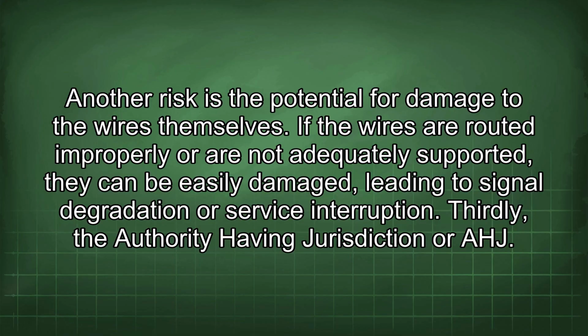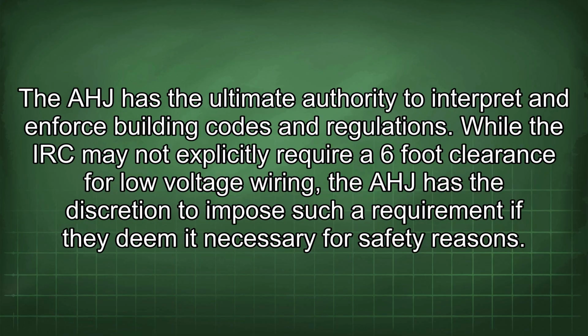If the wires are routed improperly or are not adequately supported, they can be easily damaged, leading to signal degradation or service interruption. Thirdly, the authority having jurisdiction, or AHJ, has the ultimate authority to interpret and enforce building codes and regulations. While the IRC may not explicitly require a 6-foot clearance for low-voltage wiring, the AHJ has the discretion to impose such a requirement if they deem it necessary for safety reasons.